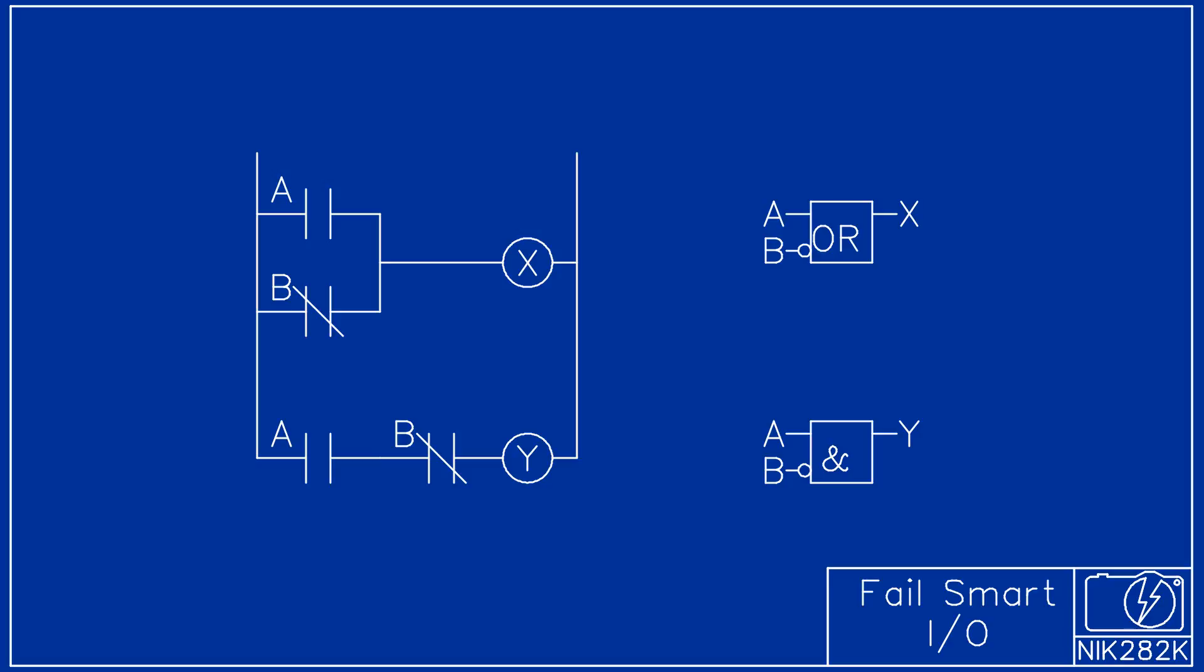The contacts in parallel work like a logical OR gate and the contacts in series act like a logical AND gate. The normally closed contacts act like an inverted input on a function block and are represented by a circle on the input.